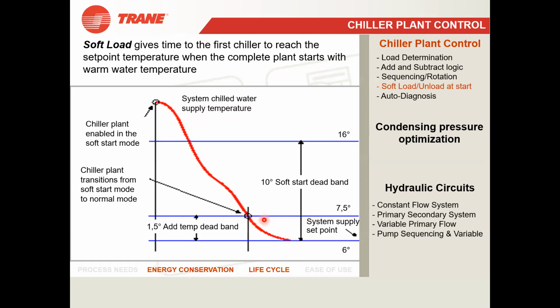It will wait until the rate of change of temperature at header level stabilizes at the set point. Suppose here is my set point. I told you that I have always considered my set point as 6 degrees and the upper dead band is 7.5 degrees. So until 7.5 degrees, it will not start any other chiller. Only one chiller will be working, and after 7.5 degrees it will run into normal operation mode, and then at 6 degrees it will be stabilized. So until one chiller gets stabilized, it will not start any other chiller. Hope I'm clear. If it is not clear, I can repeat it once again. Okay, that means I'm clear. So after reaching 6 degrees, it will be on the set point and it will be running continuously.